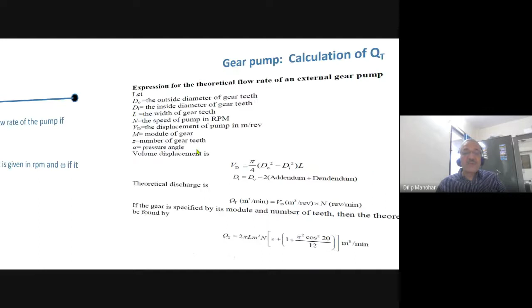Now I have taken a slide from some NPTEL notes, the formula for a gear pump. Here DO is the outside diameter of the teeth, the OD of the gear. DI is the inside diameter, the root diameter of the gear. L is the width of the gear. N is the speed in revolutions per minute. VD we calculated by this formula: pi by 4 into DO square minus DI square, into length. This is converted using the addendum. M is the module of the gear, Z the number of teeth, and alpha the pressure angle. So this whole formula is converted into number of teeth, module, and pressure angle by using appropriate conversion.